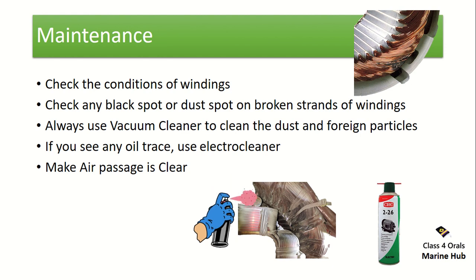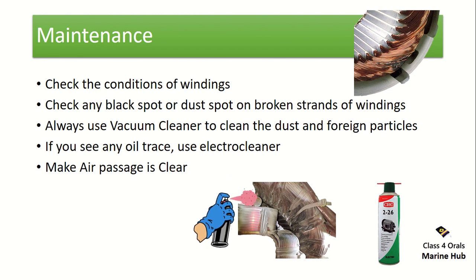If you see any oil present on the winding and on the internals of the alternator, always use the electro cleaner — spray the CRC electro cleaner and clean with a lint-free cloth, as shown in the animation. Also make sure the air passage is clear, because the alternator heats up over time and proper ventilation and cooling requires clear air passages.